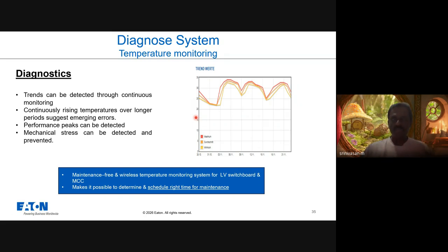So normally what will happen is, suppose the bolted joint did not have the proper torque ensured, then the temperature will shoot up. Once the temperature shoots up, it will increase further. Then it will lead to insulation failure, and insulation failure will lead to a short circuit.